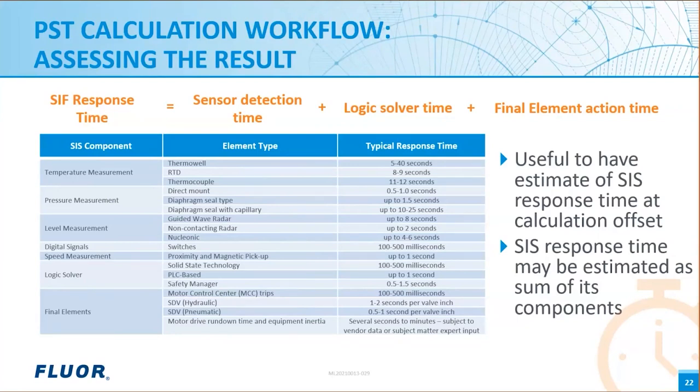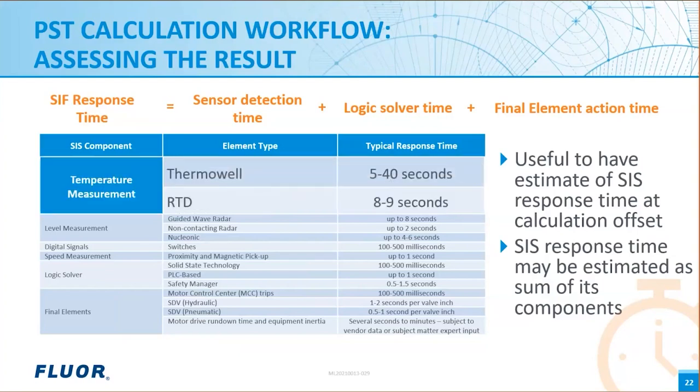But if you look carefully at the table, for example, under temperature measurement, we can see that for thermowells, the response time can be as long as 40 seconds, which obviously leads to potentially a very long system response time. And when we need to apply a 100% margin to that, we can see that we need a very long process safety time indeed.